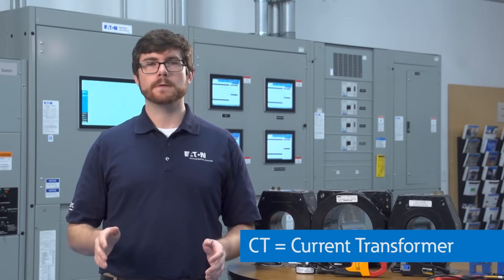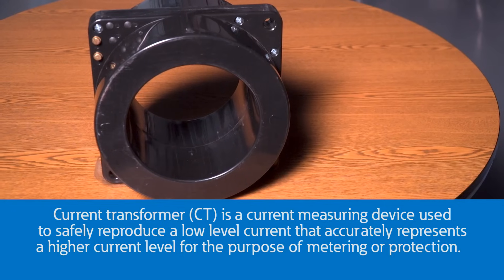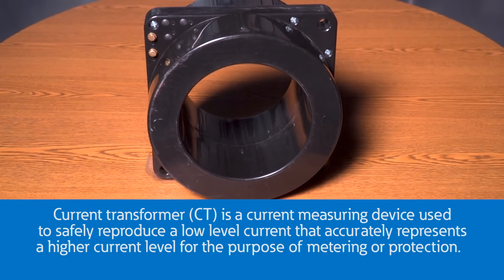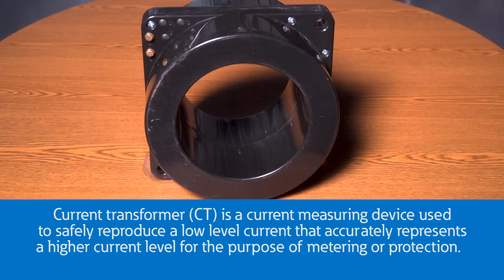Yeah. First, let's back up a little bit and define what a CT or current transformer is. A CT is a current measuring device that is used to safely reproduce a low level current that accurately represents a higher current level for the purpose of metering and protection.